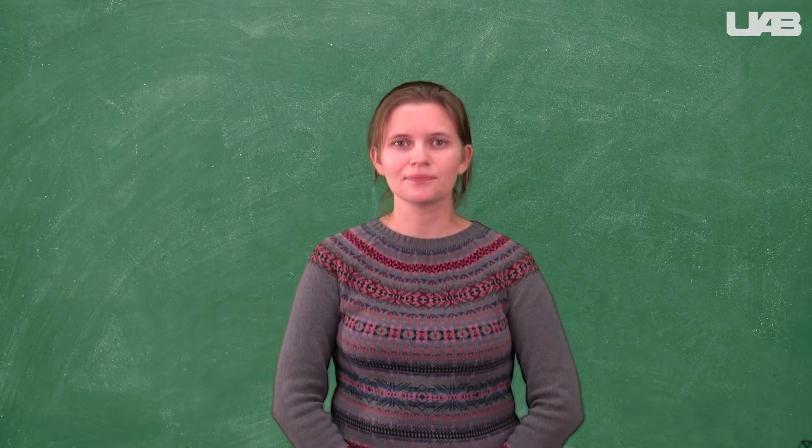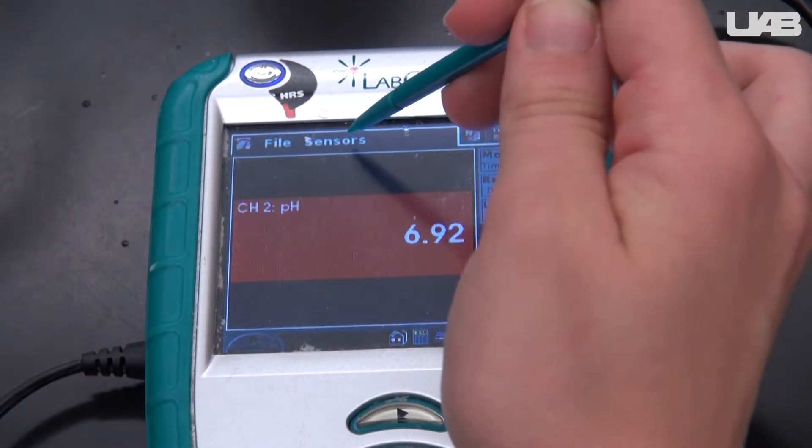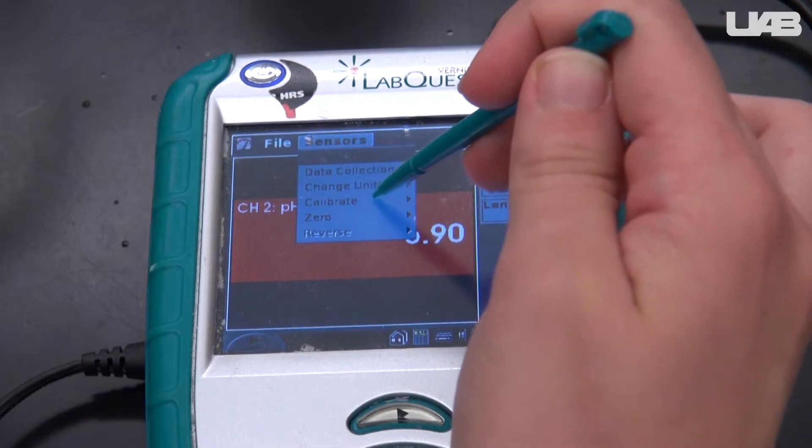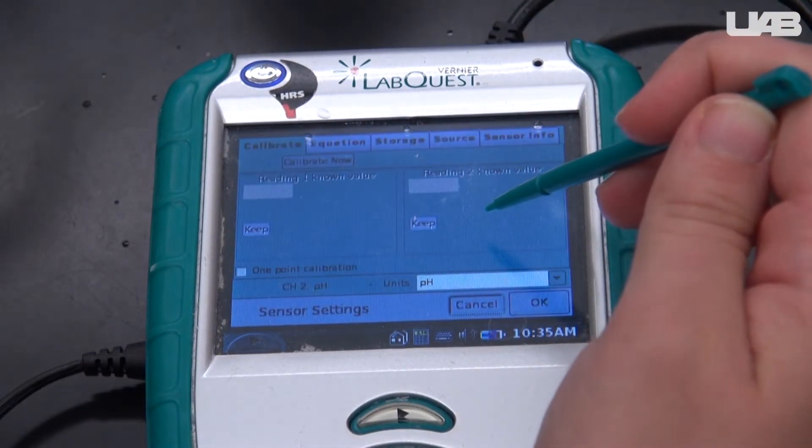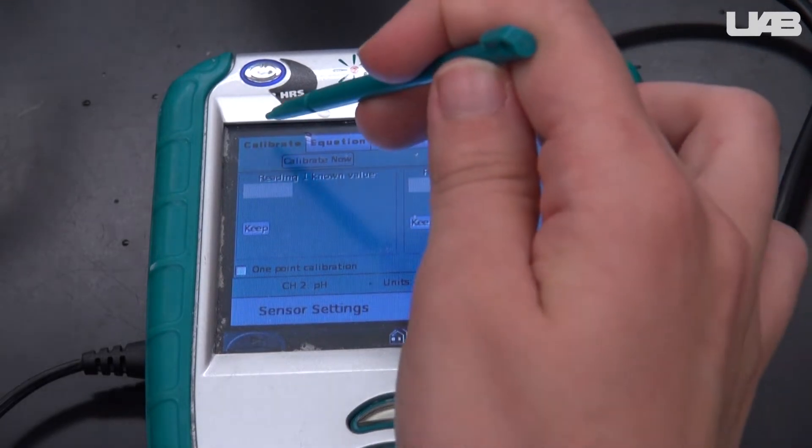Then look at the pH meter. Select Sensors to open the drop down menu. Then select Calibrate. Then click the box that pops up to the side. A new screen will appear. Select Calibrate now.